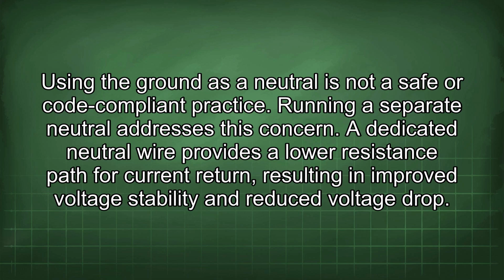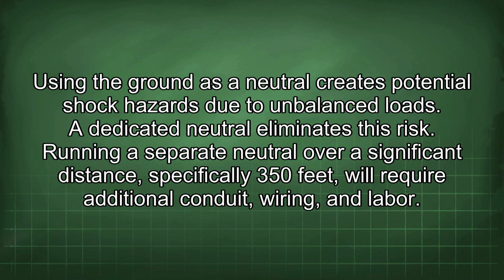A dedicated neutral wire provides a lower resistance path for current return, resulting in improved voltage stability and reduced voltage drop. Using the ground as a neutral creates potential shock hazards due to unbalanced loads. A dedicated neutral eliminates this risk.